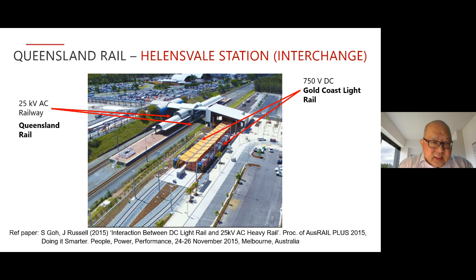And on the DC track, the light rail, a DC stray current collection mat was installed, but not connected up. So all the conduits and everything are there. If there's any issue, we can then connect it up to collect the DC stray current instead of letting it flow onto the AC railway. Myself and Jeff Russell wrote a paper in 2015, and you can see on the screen there's an awful lot of standards that we compiled, including EN 50122 Part 3 that deals with the interface between AC and DC systems next to each other.